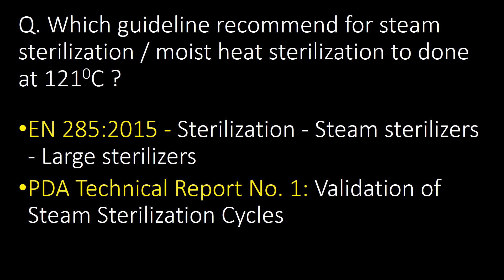Which guidelines recommend steam sterilization or moist heat sterilization to be done at 121 degrees Celsius? EN 285 and PDA Technical Report Number 1 are the guidelines that recommend steam sterilization or moist heat sterilization to be done at 121 degrees Celsius.